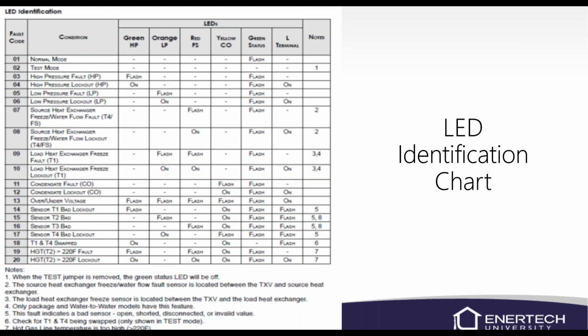Here is the chart in the manual that'll tell you what the fault means, and it'll kind of give you some notes on what the fault may be. Let's say 14 is a sensor T1 bad, and you're in a lockout. So you're going to have a green high pressure light flashing, and the condensate overflow, the fourth light down, is on. That will give you a note, note number 5, which tells you this fault indicates a bad sensor: open, shorted, disconnected, or invalid value. So it'll kind of give you an idea of what you should be looking at. And it'll tell you what your T1 to your T4 sensors are, so in case you forget what those sensors are, you don't have to trace them out. It'll kind of tell you.